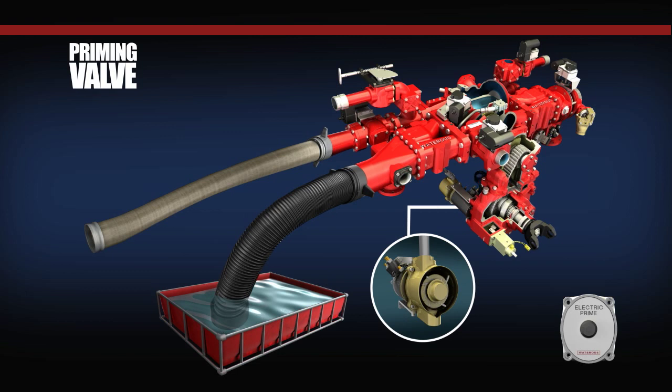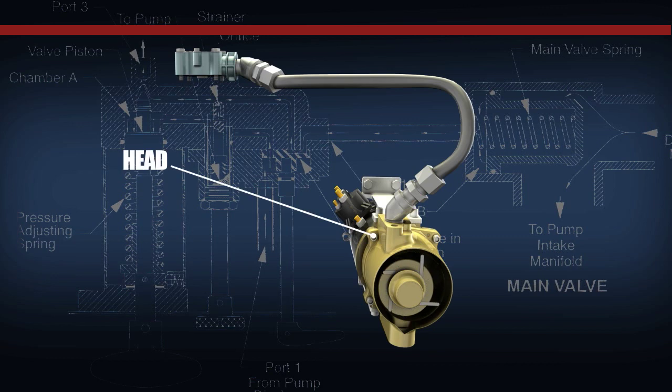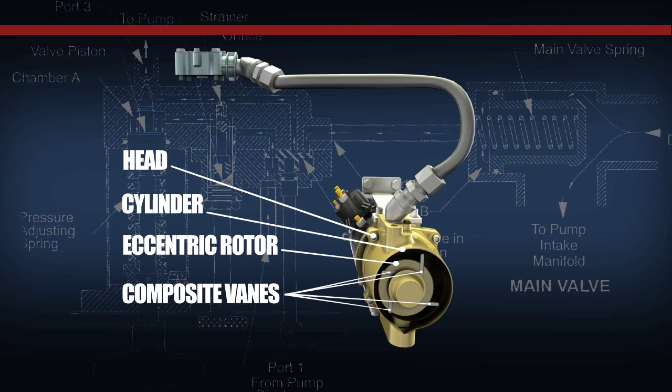Once the solenoid on the priming motor receives power, it closes and allows battery voltage to engage the priming motor, which results in its internal shaft rotating at approximately 2300 RPM. The Waterous VPO model priming pump is direct coupled to the priming motor and consists of a head, cylinder, eccentric rotor, and four composite vanes that slide in and out as the priming pump is operated.